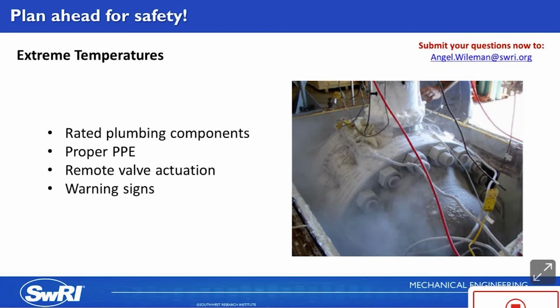The area should be clearly blocked off so that you notify operators working nearby, and you want to post warning signs around the setup that provide the temperature range. The valve shown here was tested to cryogenic temperatures, but some temperatures aren't so obvious from the outside what kind of extremes you're at, so it's really important to notify people nearby. I would also suggest becoming familiar with the safety data sheets of any insulating materials you're using, because many of these will irritate the skin or the lungs if inhaled.